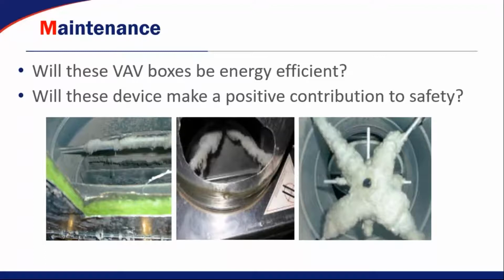And the answer is no, because what typically happens is when the flow sensors get clogged up, they have an inverse relationship to how much dirt is on them. So the dirtier they get, in the case of an exhaust valve, if the lint clogs up the flow sensors, that exhaust valve is going to go open. And if you have a supply VAV box tracking an exhaust box, as that VAV box goes open, it's still reporting a low flow through it because the sensor is still clogged. So if your supply valve is tracking that low flow from the exhaust valve, your supply valve is going to track to a low flow. Meanwhile, your exhaust box is going to be 100% open.